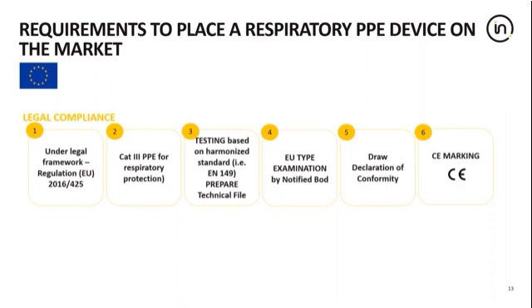The technical file should be submitted to the notified body as part of the certification procedure. The content of the technical file should again include information such as the bill of materials, design drawings, label files, packaging files, test reports, and quality management system and relevant quality control reports. The importer should hold the technical file, or again, they may have an authorised representative to hold the documentation. And then a declaration of conformity can be prepared, which includes the name of the importer or relevant authorised representative.